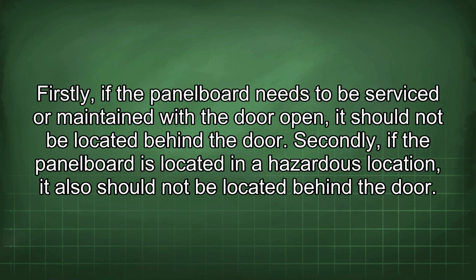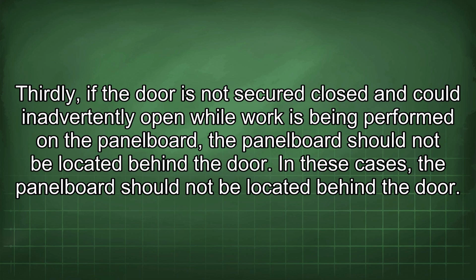Firstly, if the panel board needs to be serviced or maintained with the door open, it should not be located behind the door. Secondly, if the panel board is located in a hazardous location, it also should not be located behind the door. Thirdly, if the door is not secured closed and could inadvertently open while work is being performed on the panel board, it should not be located behind the door. In these cases, the panel board should not be located behind the door.